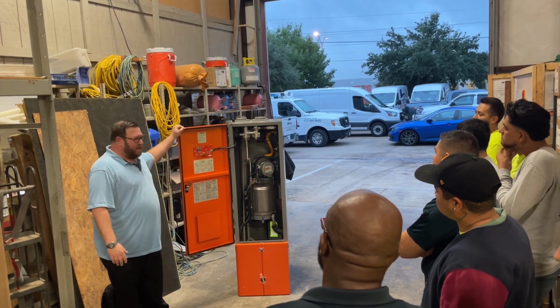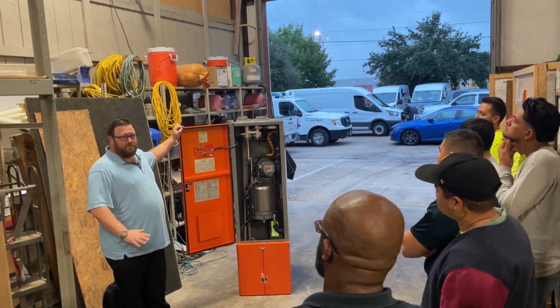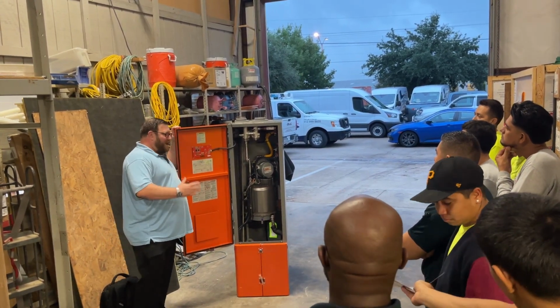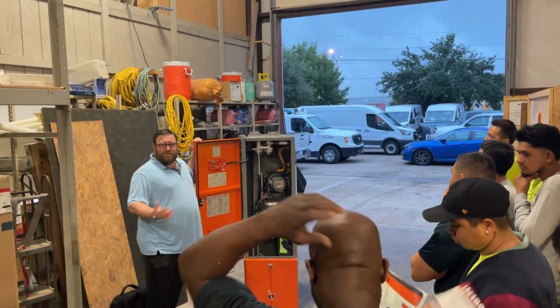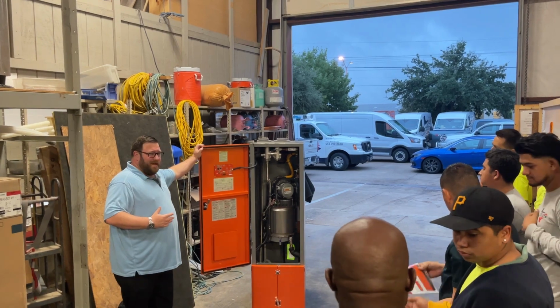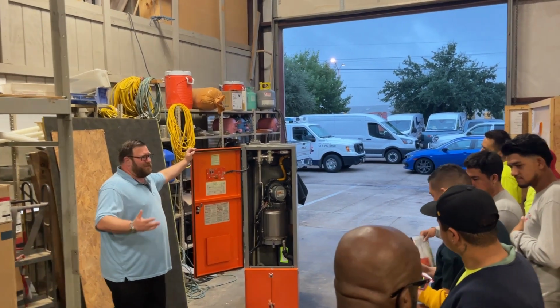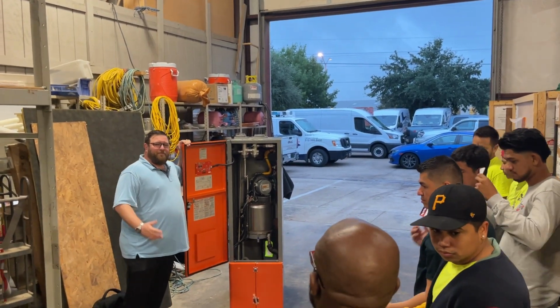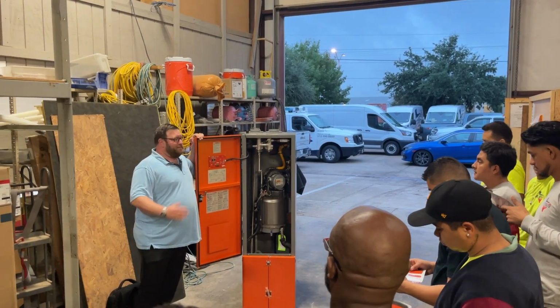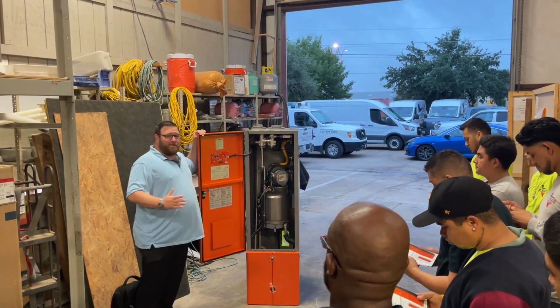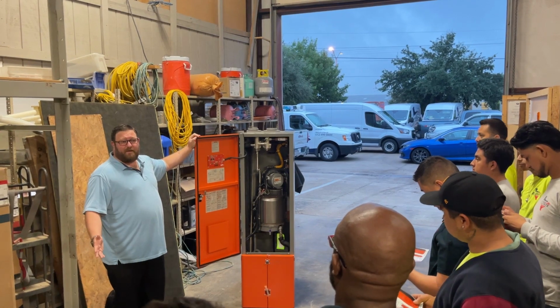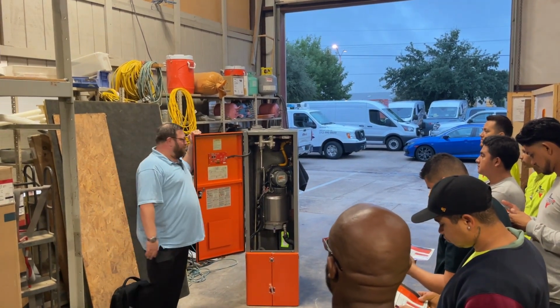This is a direct replacement for a 100-200, straight up. Normally with tankless you need 1.5 to 2 inch, but with this you don't. The reason is A.O. Smith, Green, whoever it is, their water heaters put out about 330 gallons per hour. So does this. If we were talking residential, we'd talk gallons per minute, but commercial is gallons per hour, that's what's important.